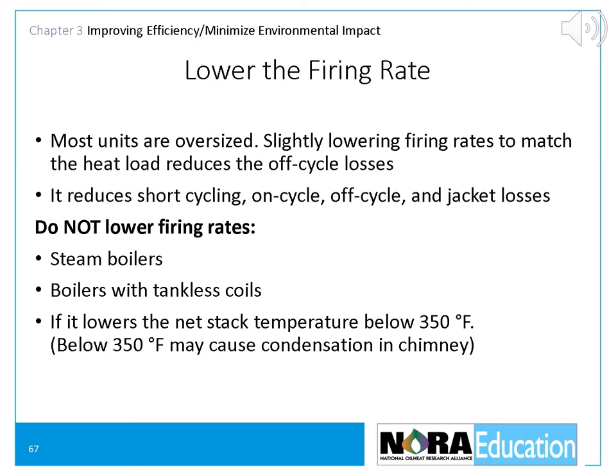Another strategy is to lower the firing rate. If the unit is overfired, the heat exchanger does not have time to remove useful heat because too much heat is being produced in a short time period. Overfiring causes the burner to short cycle, which causes many problems. A common cause of overfiring is that someone has increased pump pressure to get better atomization without reducing the nozzle size. Remember, whenever you increase pump pressure, you increase firing rates, so you have to downsize the nozzle. Excessive firing rates cause problems for boilers and furnaces — firing rates higher than the heating requirement increase off-cycle losses. The solution is to reduce the nozzle size, but not below manufacturer's recommendations and not below what is necessary to keep the net stack temperature above 350°F.